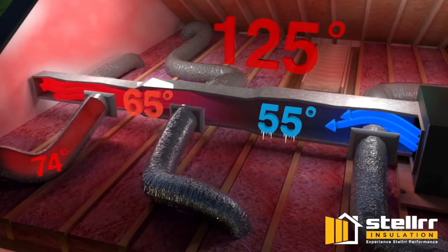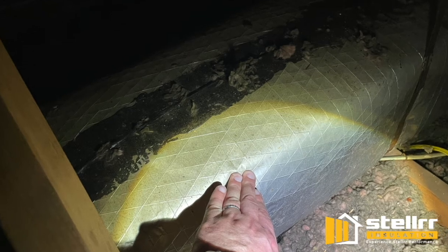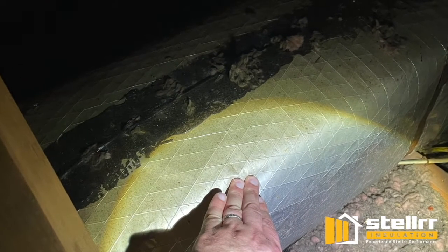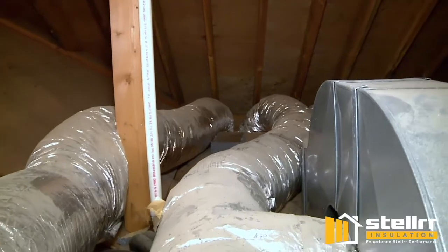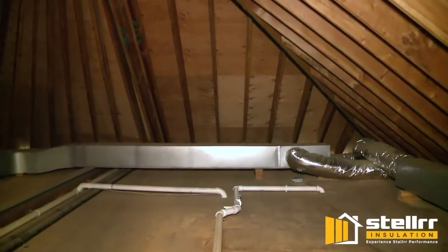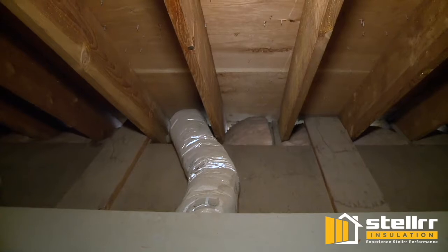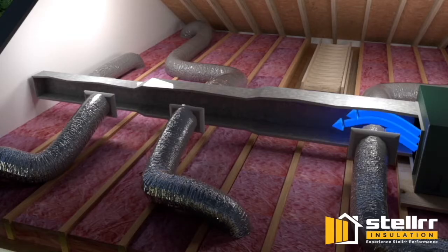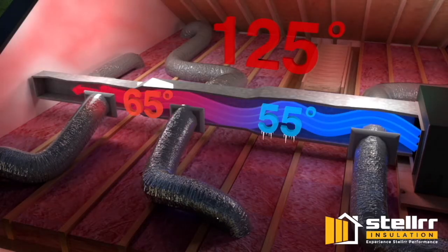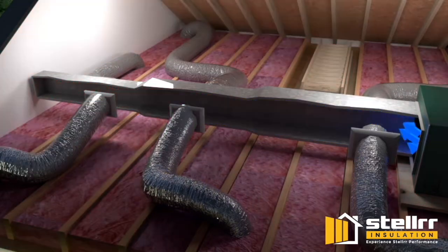Your ductwork has a thin fiberglass wrap between the 55-degree air and the 125-degree air. As the air that you paid to cool travels through that hot ductwork, it heats up, meaning you're blowing 65 to 75-degree air into the rooms that are furthest away from the air handler.